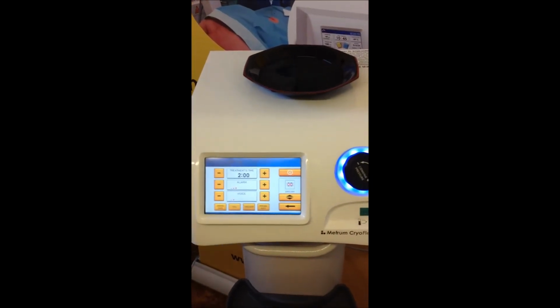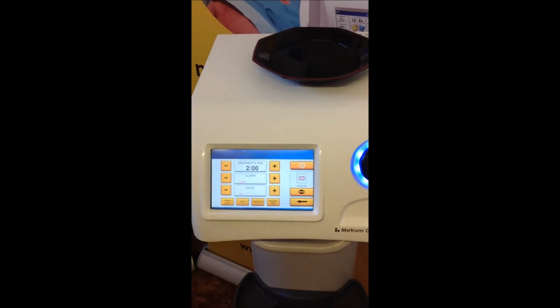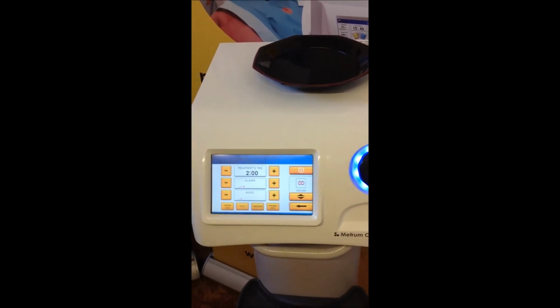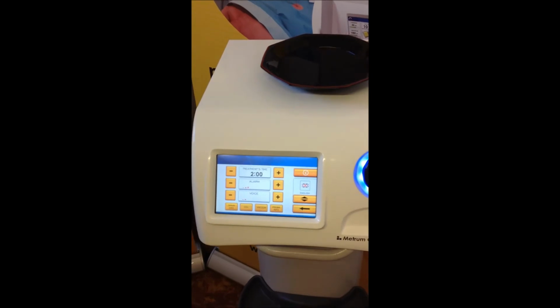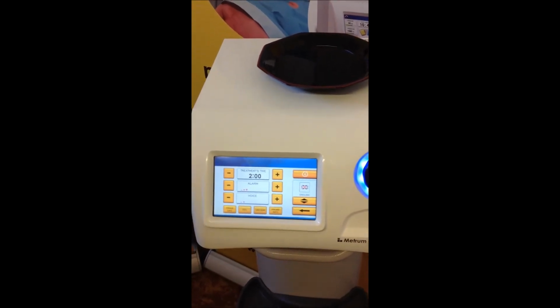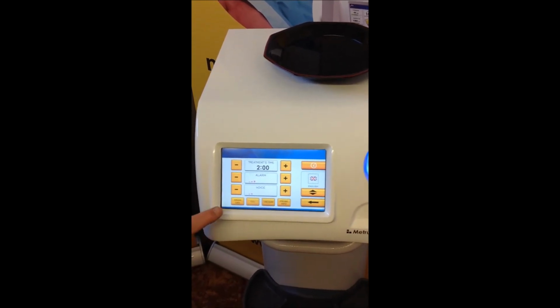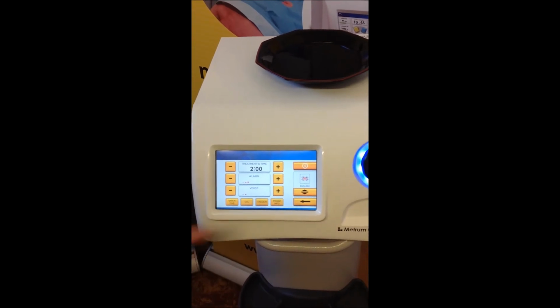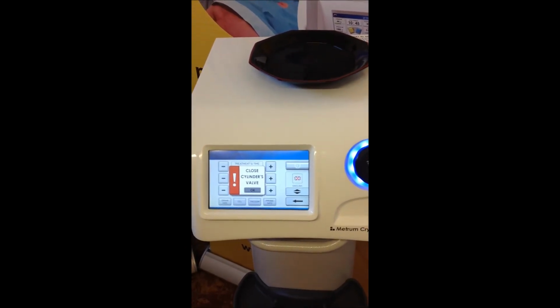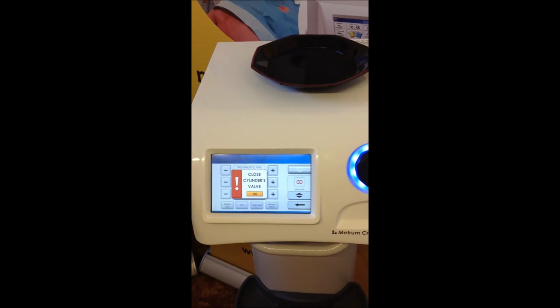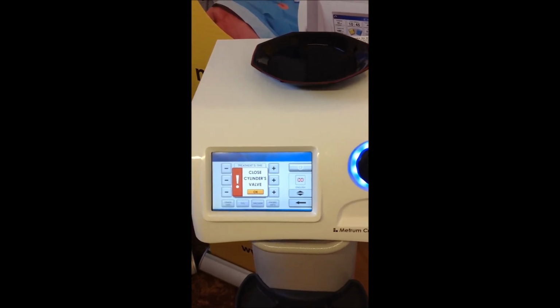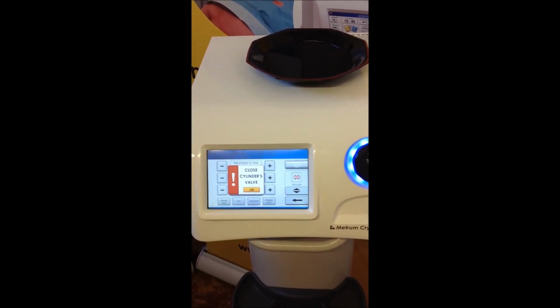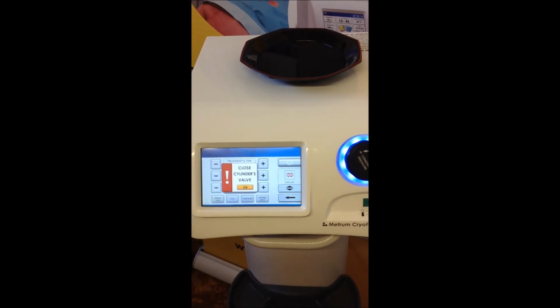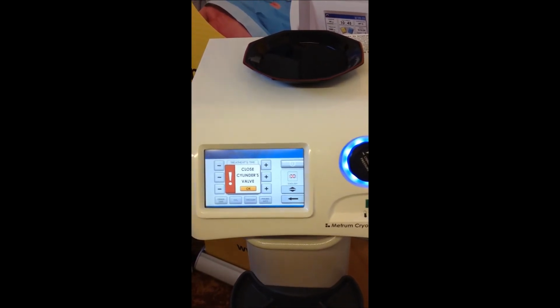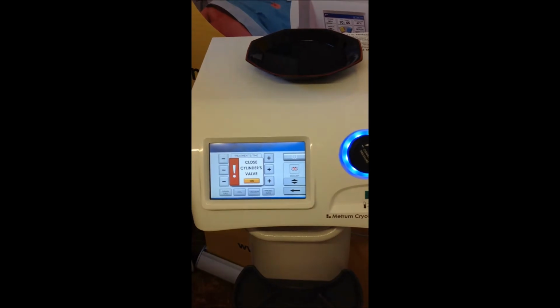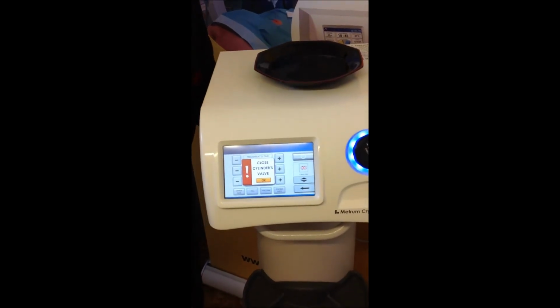I'm going to do something now that I should not normally do, but I'm going to do it anyway, just to show you what people can sometimes forget. When I push the drain gas button, look what happens. Close cylinder's valve. It says that we should close the valve of the CO2 bottle, which normally should be done when you drain the gas. We didn't do that, but we're going to do it now because the machine told us to do so. And we always listen to machines.